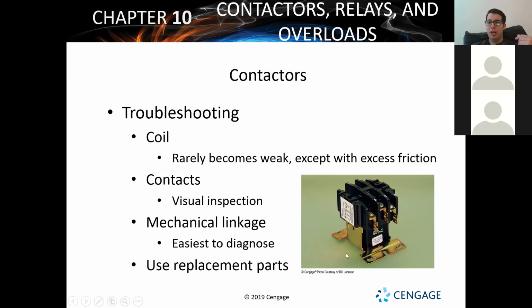I've been shocked by that before. That was one of the ways I found out when I went to a house and they said, oh, our AC is not working. I go outside and the outdoor unit's not working. Well, let me go check the capacitor, because a bad capacitor is a really common problem in the summertime for outdoor air conditioning units. And the capacitor's good. So I'm like, all right, looks like the contactor's getting 24 volts. And then I touched it, and right here on this base where the coil was touching, I got a little tiny shock. I was like, okay, that did not feel like 240. Otherwise, I'd have been flown back. Definitely felt more like 24. Felt like that little tiny voltage.